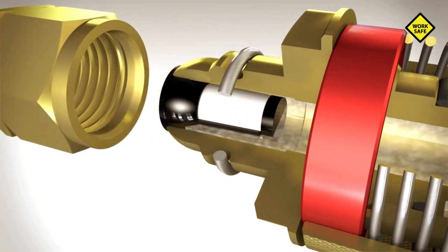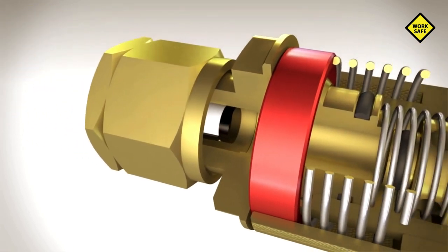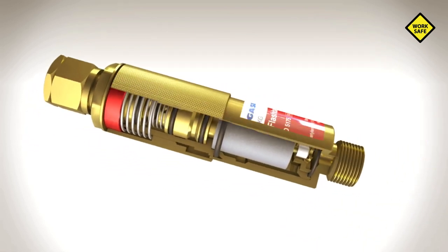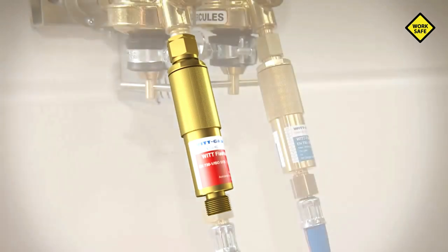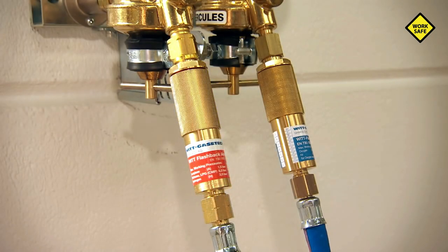The flashback arrestor is effectively protected against dirt by a filter in the gas inlet. Flashback arrestors from WITT are compact and robust and can be installed anywhere, irrespective of orientation. For maximum safety, the fuel gases and oxygen supply should be provided with a flashback arrestor. In many countries, this is already required by law.